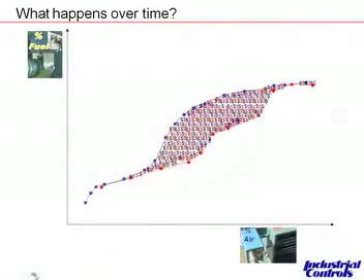boiler is initially commissioned or when it's tuned, the person doing the work will use a combustion analyzer and find the sweet spot over maybe 4 or 5 points from low to high fire, and we'll set the fuel-air ratio to where he or she believes it needs to be to maintain safe, clean combustion. But that's pretty much a snapshot in time, right?